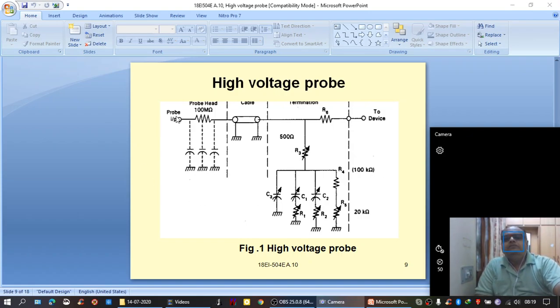So by using this high voltage probe head having 100 mega ohms, the internal current will be limited. It flows through the cable and through the terminating end it reaches the device. And depending upon that reduced current, the normal voltmeter will give the value. And that value has to be multiplied by a factor. By what factor? By the factor by which the voltage is reduced. Suppose the probe is 10 is to 1 scale, here you have to multiply the value with 10.